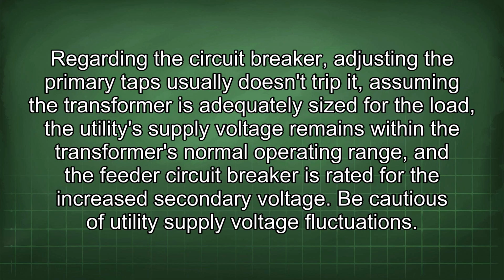Regarding the circuit breaker, adjusting the primary taps usually doesn't trip it, assuming the transformer is adequately sized for the load. The utility supply voltage remains within the transformer's normal operating range, and the feeder circuit breaker is rated for the increased secondary voltage. Be cautious of utility supply voltage fluctuations.